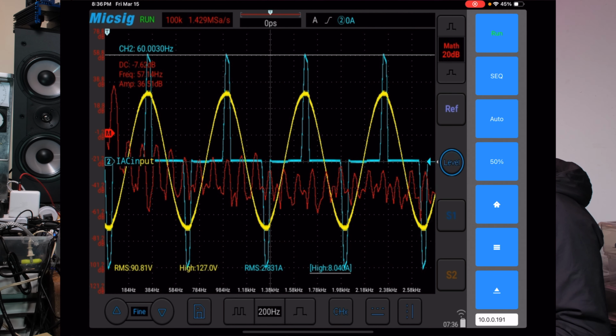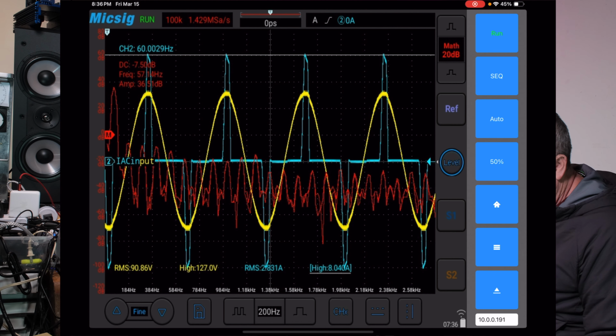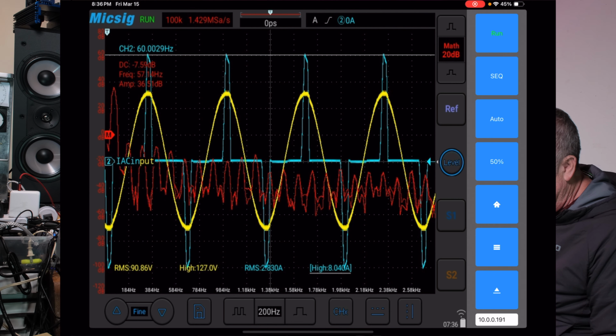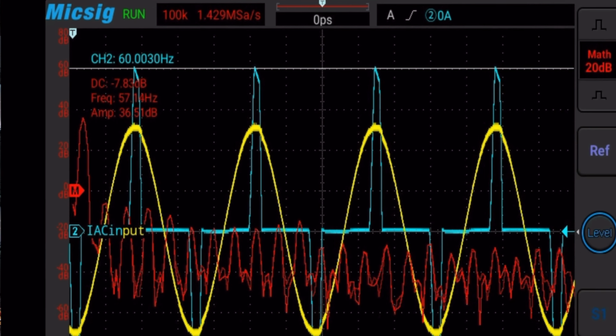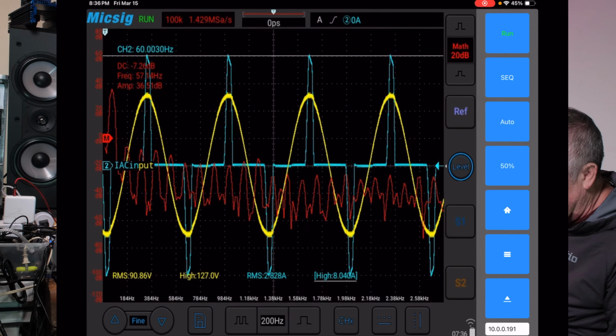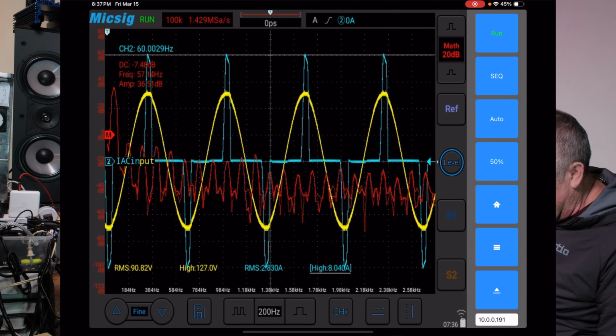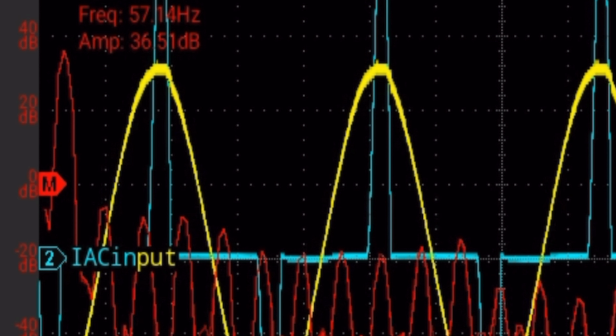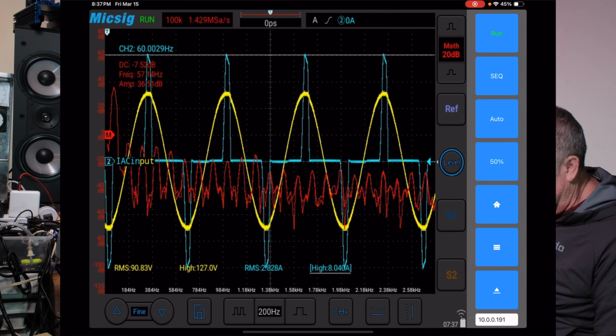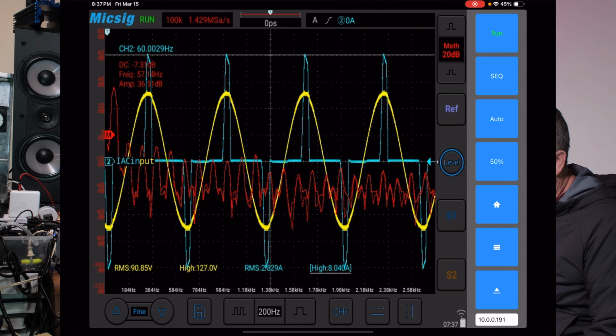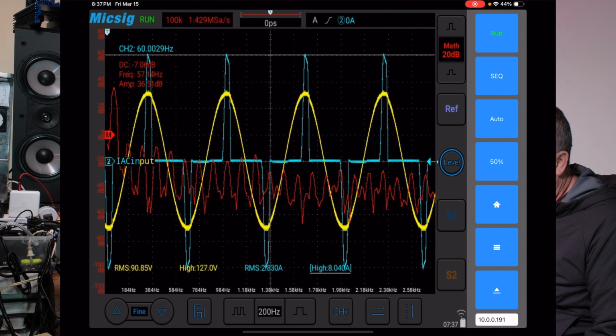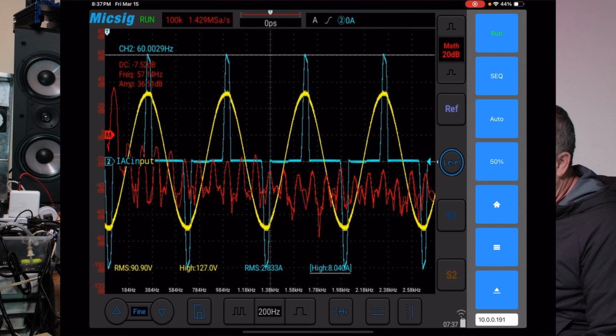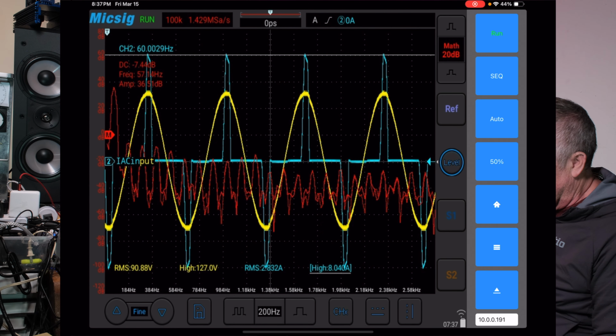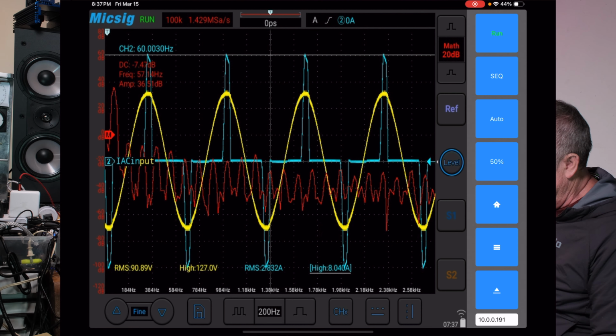Okay, I'm going to bring the signal down right there, so that's 0 dBs, where you see the M on the left side of the screen. 60 hertz is going up to 36.5 dBs, you can see the numbers there. The harmonics are pretty low, down below 0, around -10 dB, and then they drop off to -20 about the middle of the screen. So that's the voltage. The sine wave looks pretty clean, right? We're going from 36 down to around -10 or -5, so we've got at least 40-something dBs between the peak and the first harmonics. That's looking pretty decent.